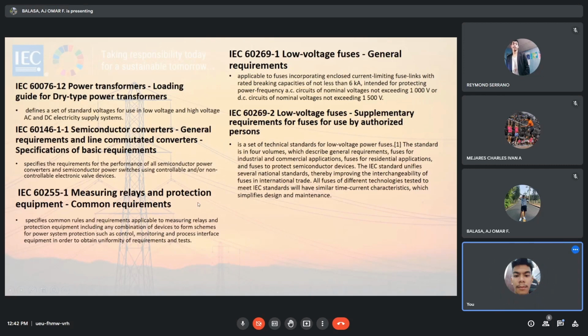Next is IEC 60269, Part 1, Low Voltage Fuses, General Requirements. Applicable to fuses incorporating enclosed current-limiting fuse links with rated breaking capacities of not less than 6 kA, intended for protecting power frequency AC circuits of nominal voltages not exceeding 1000 volts or DC circuits of nominal voltages not exceeding 1500 volts.